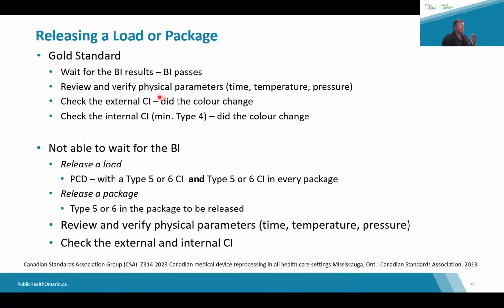Review and verify that the physical parameters, the time, the temperature, and the pressure were correct. And this is why we really want people to have either a printout or a USB where you can have an electronic record of the physical parameters. Because if you only have the little display, then you have to have somebody stand there for the course of the cycle to make sure that you're hitting the right physical parameters, and that's a lot of time. So it's better to have a printout or the USB.